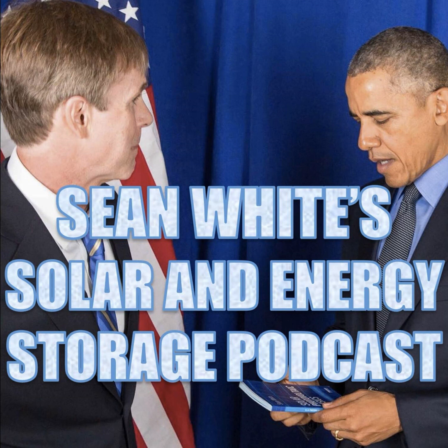And the reason that they did this was for you O&M people out there. So when you swap out an older inverter, say a grounded inverter, for a newer inverter, say an ungrounded inverter, you don't have to go rewire the system. So what you can do is just swap it out, and you can just leave overcurrent protection on one single polarity. How convenient.